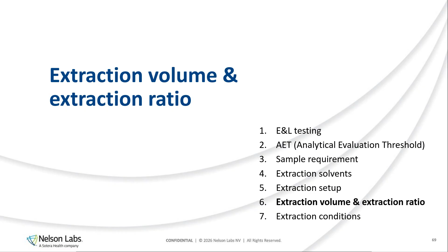So now let's get to the volume and the extraction ratio. So we would start at ISO 10993 part 12, and I see it's a bit gone here, but it's part 12. There's a table in it, and it's the only standard that mentions an extraction ratio. But as you can see, it's just a table that says the extraction ratio to use. And for example, in most cases, most devices that have a thickness larger than 0.5 millimeters can use an extraction ratio of 3 centimeters square per milliliter.